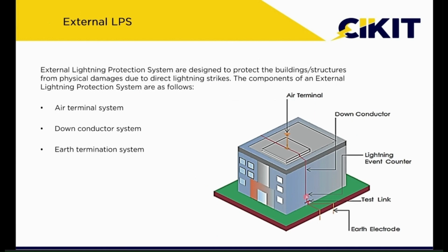Then the down conductors act as a bridge between the air terminal and the earthing. They simply pass the energy from the air terminal to the ground. And earthing dissipates the energy into the ground without increasing the ground potential. These are the three main components of a lightning protection system. Apart from this, there are two optional items. One is test link, which is used for maintenance purposes, and the second one is the counter. The lightning counter is a registering device which is used for registering the number of lightning impulse currents flowing through the particular conductor. It does not do anything else. These readings are used for performing root cause analysis, for analyzing the failure reasons.